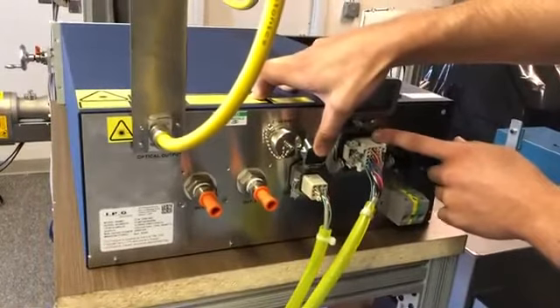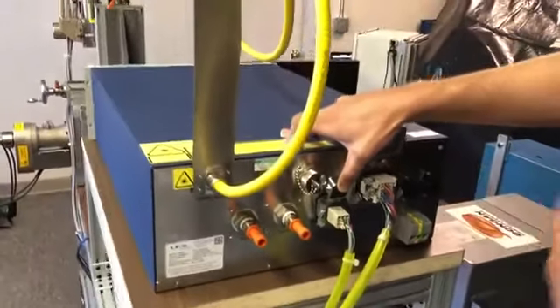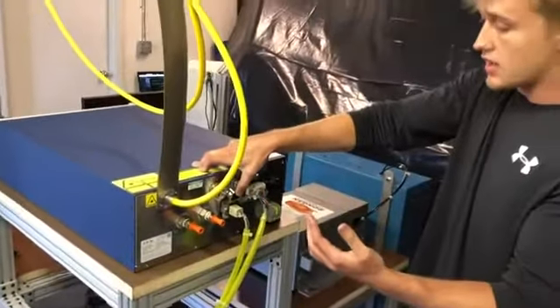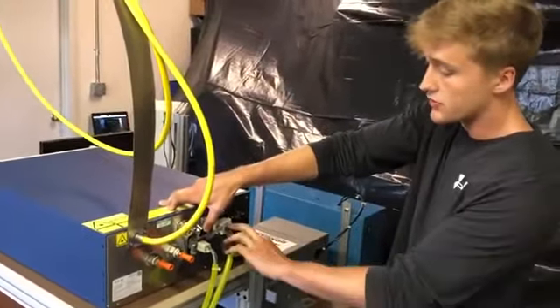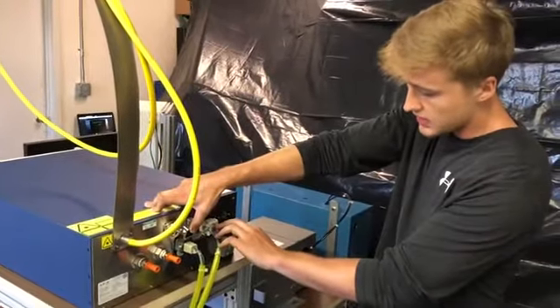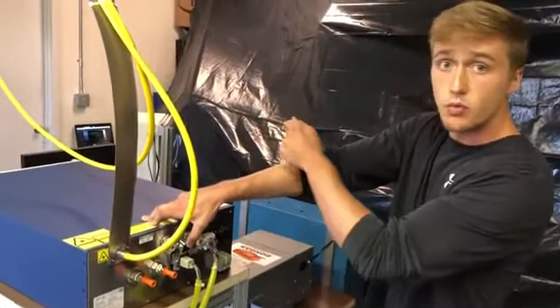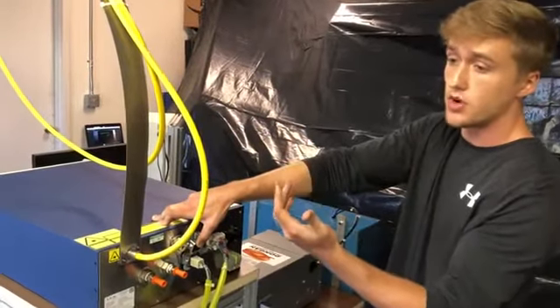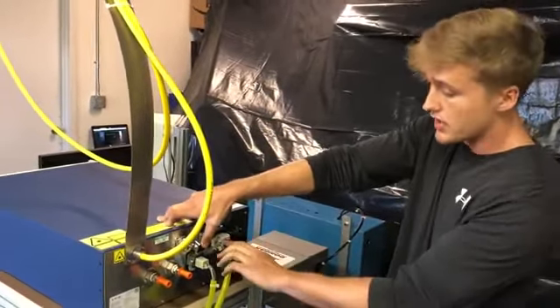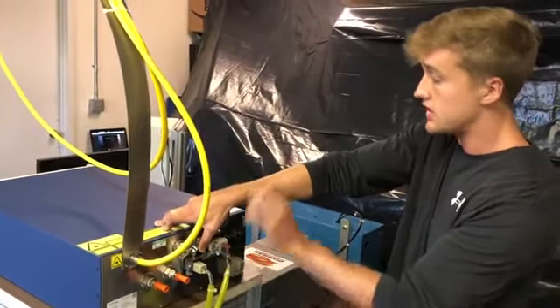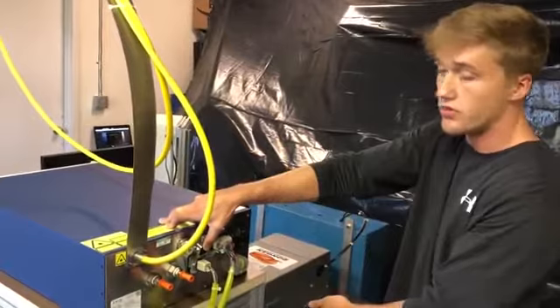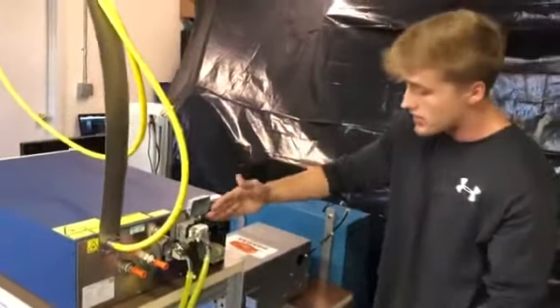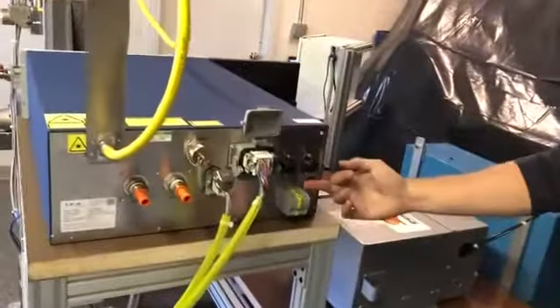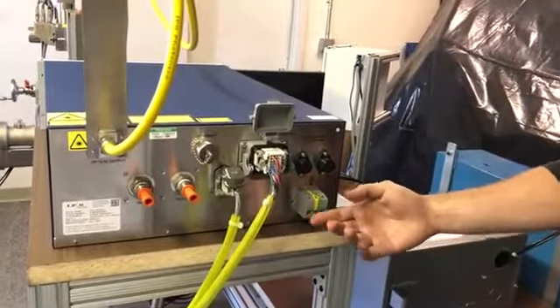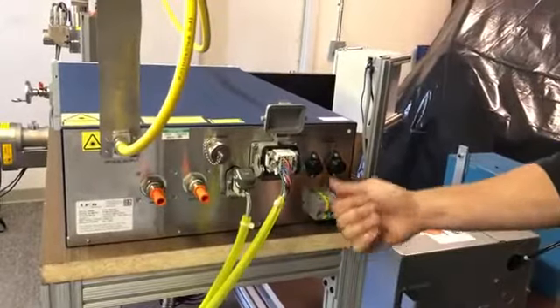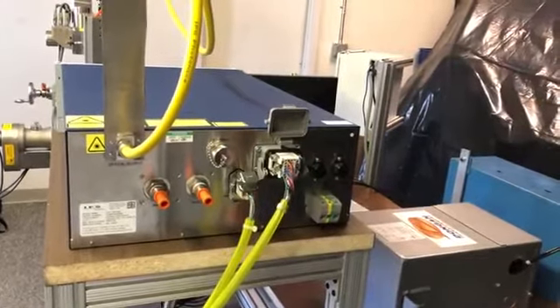Here you have your 25-pin connection. This holds all your I/O, all your diagnostics, inputs, outputs, analog outputs, analog inputs. The only difference is this second line is all referred to as the remote key switch on the front, that determines whether you are in remote or local mode. And then you have your top 4 pins, and that's the e-stop on the front, which will lead back to one of our safety relays. On the right here, you have your 2 internal fuses as well as your power lines. This is 240 single phase power, so you have your 2 lines and then ground, which will lead back from our controls cabinet.